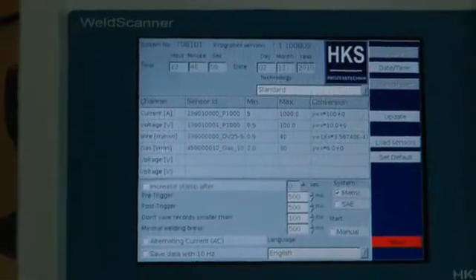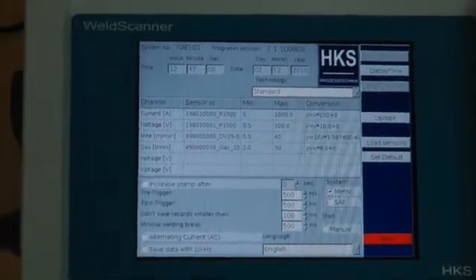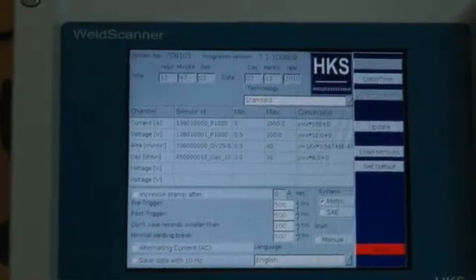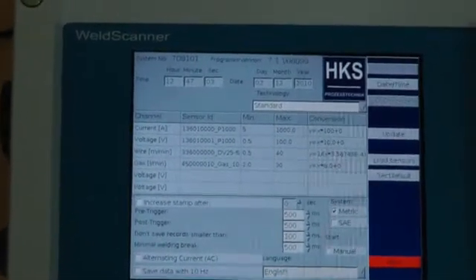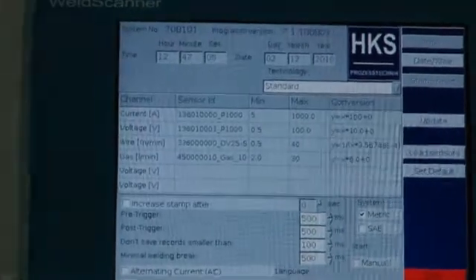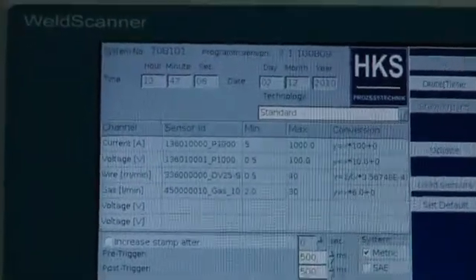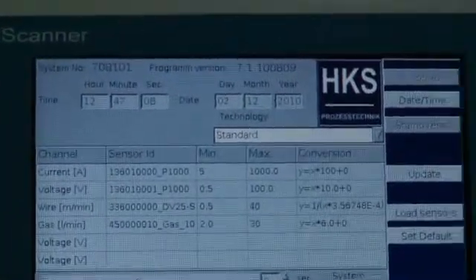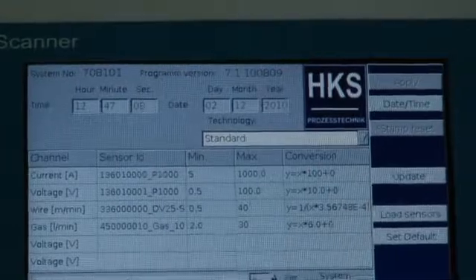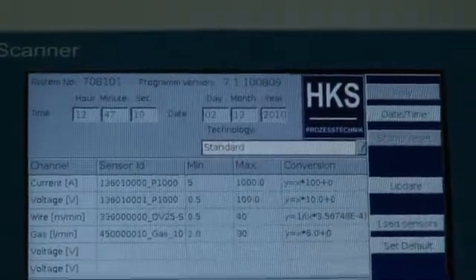That means we start recording the welding process when the current exceeds, for example, 20 amperes, but we also store data for a pre-trigger time before the start and a post-trigger time after the start of the welding process.